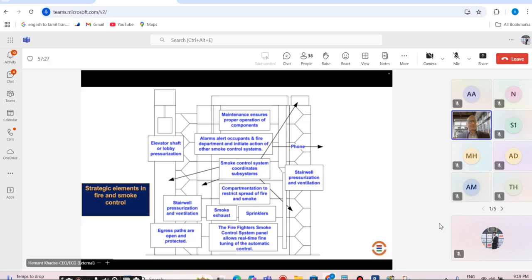So this is typically the integrated systems, how it has been designed in coordination with building engineers, and especially when you have elevator, staircase, and the connected lobby also has pressurization, how it is going to be integrated, how your smoke control systems can act as one system to activate multiple smoke zones, taking the input from fire alarm, how we are going to use the cross zone so that you can reduce the activation of smoke management.